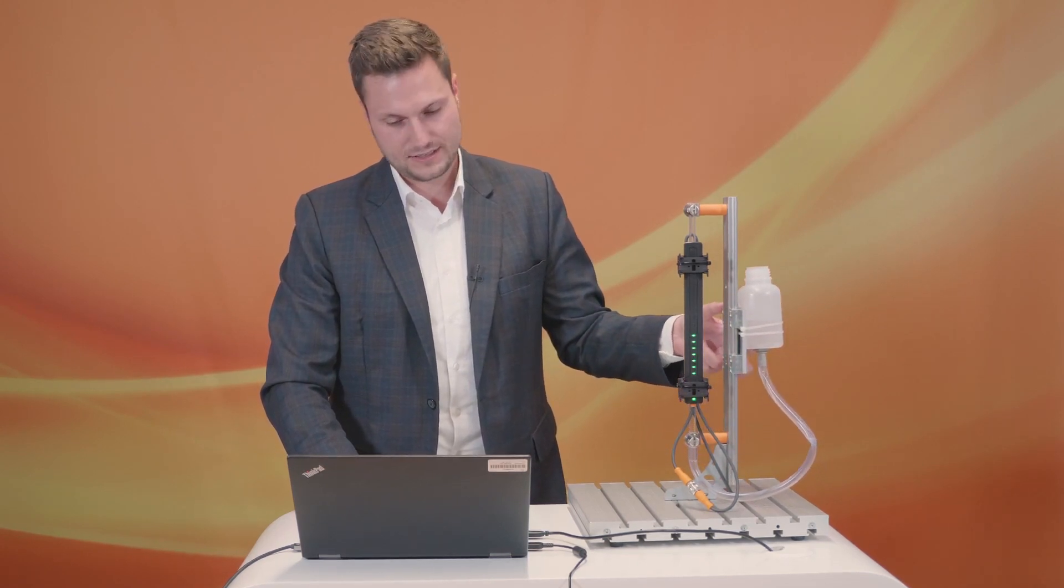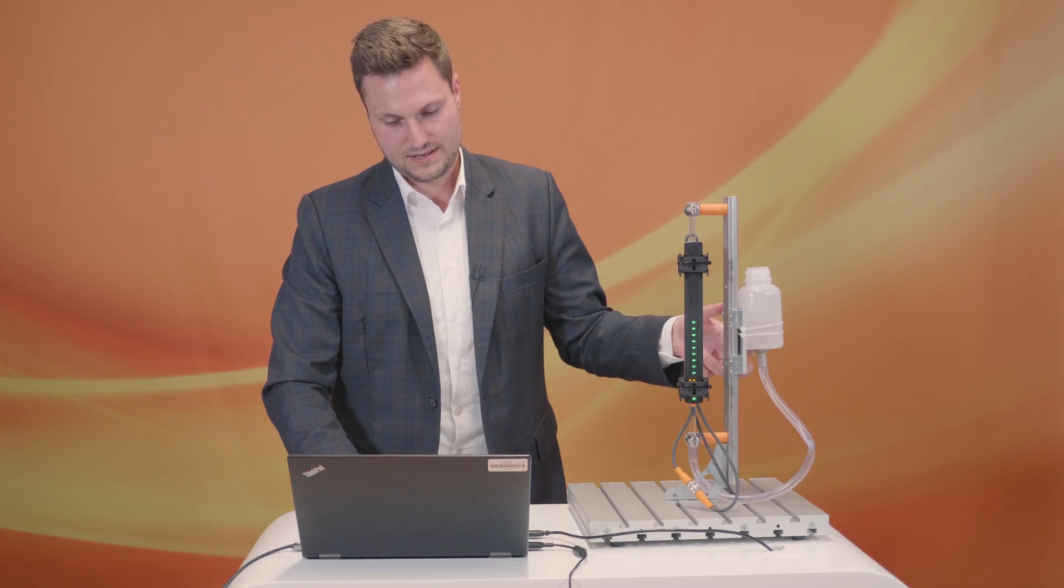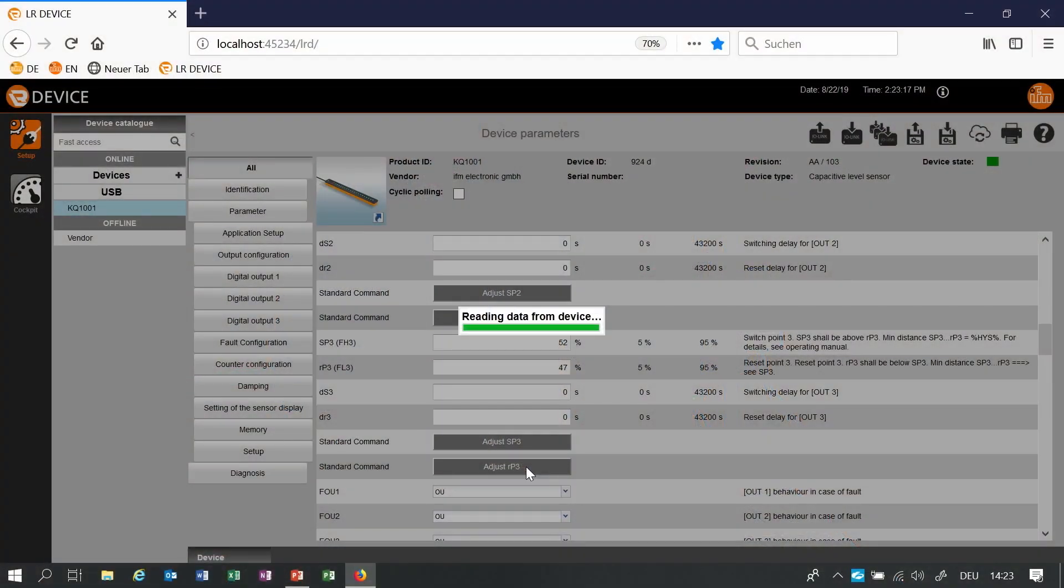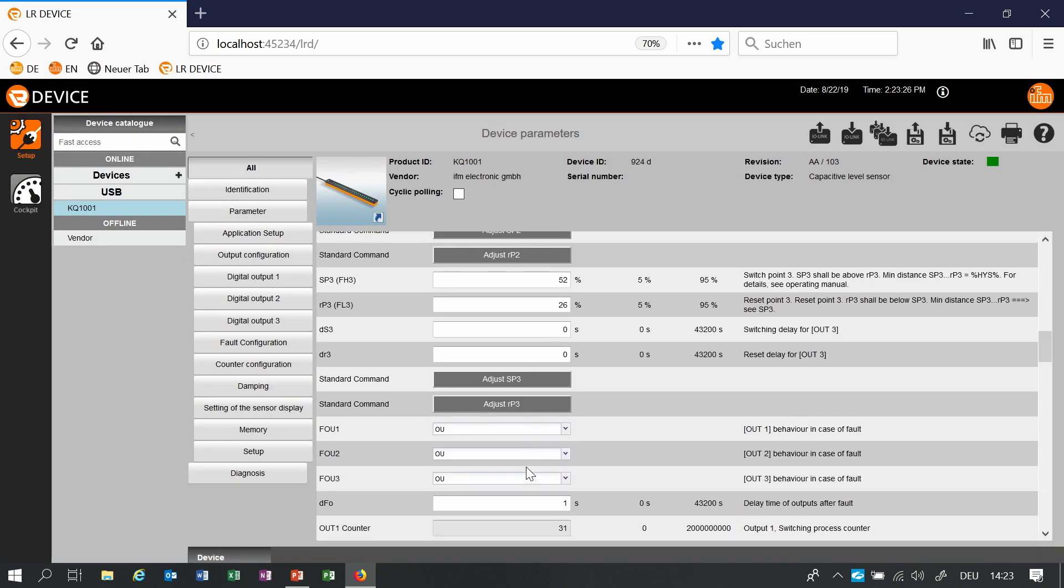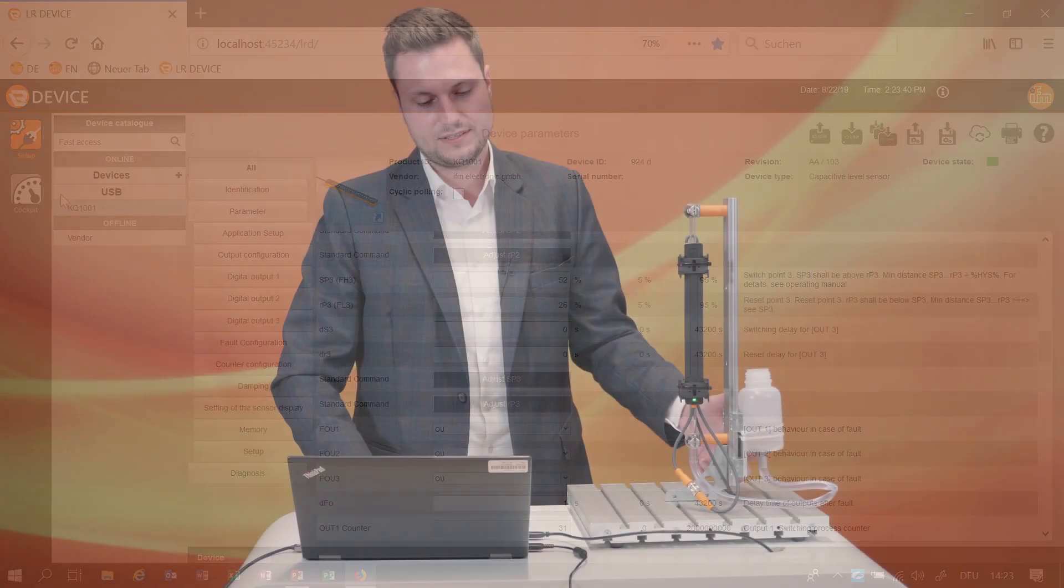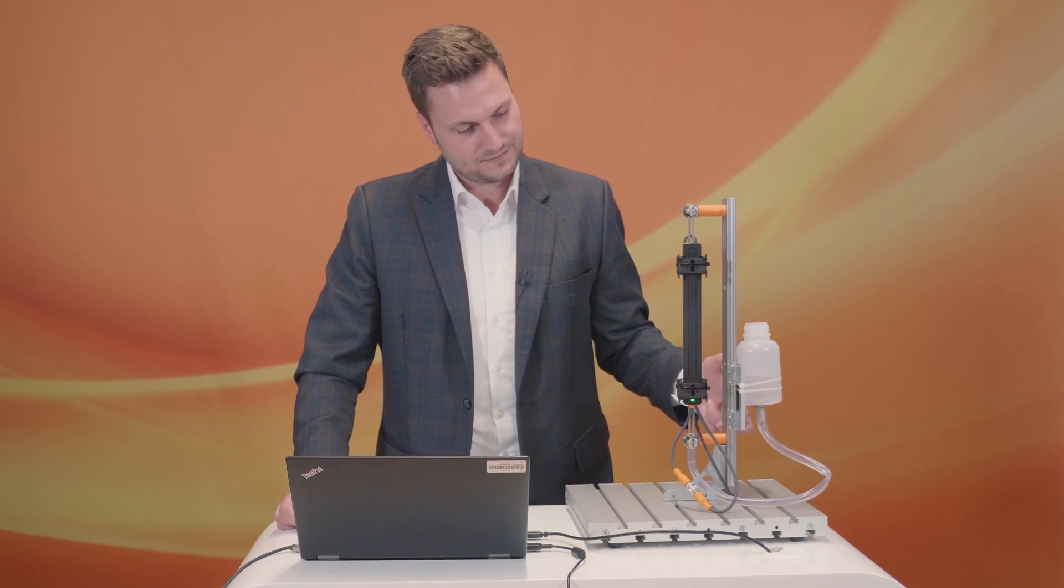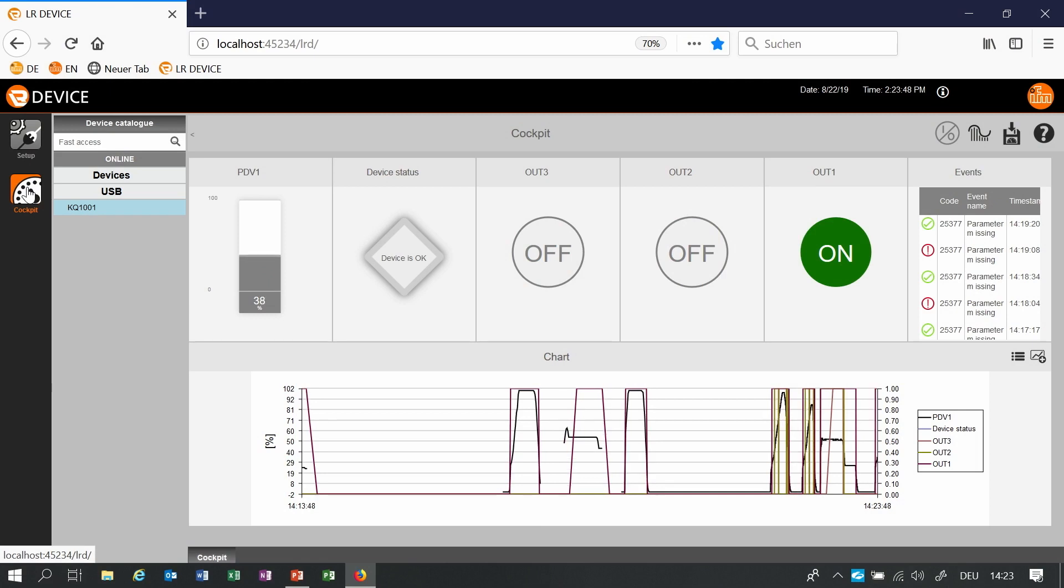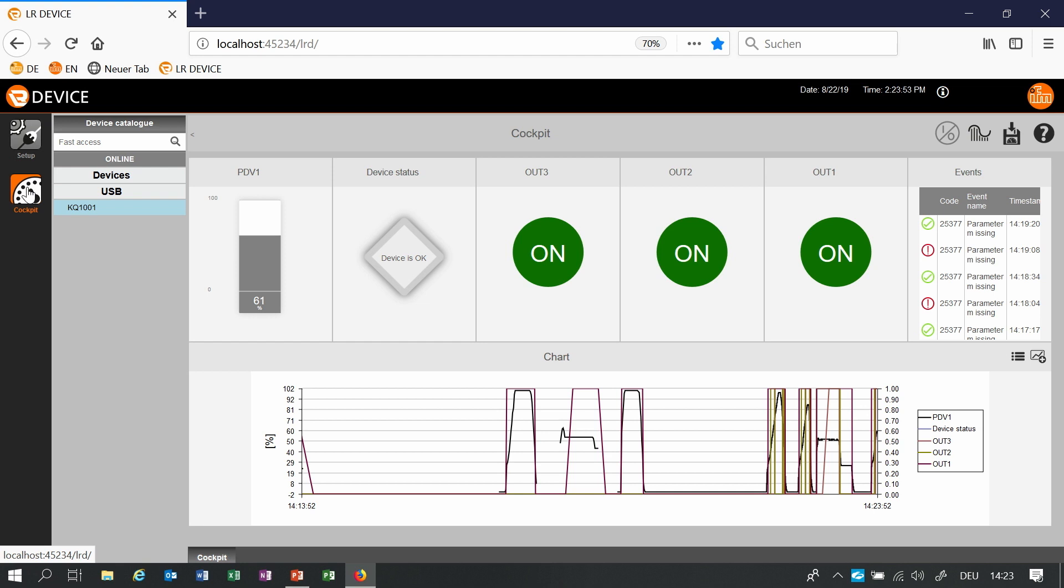We are also able to teach a level. For example in this case I set it as set switch point 3. The sensor is detecting the level right now and is saving the data. In this case it was 52 and we also can set the reset point. Maybe here. The switch on point is at 52. The switch off point or the reset point is at 26. Let us check.